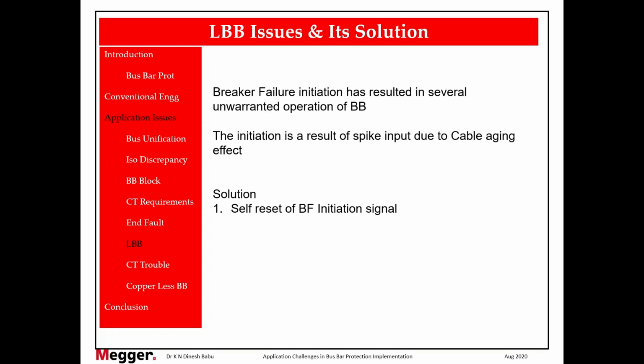So after 200 milliseconds, the bus bar will be tripped. So first point: reconfigure and make this breaker failure initiation signal as self reset. Point number 1.